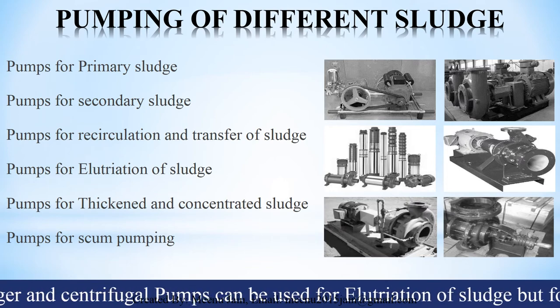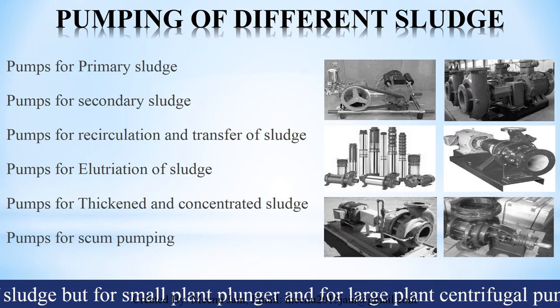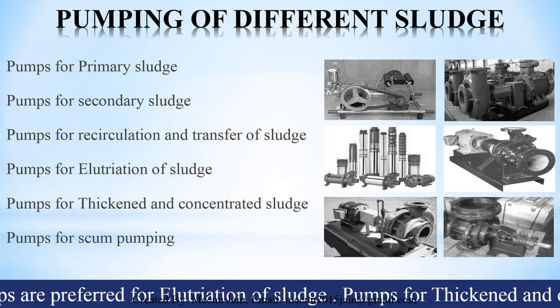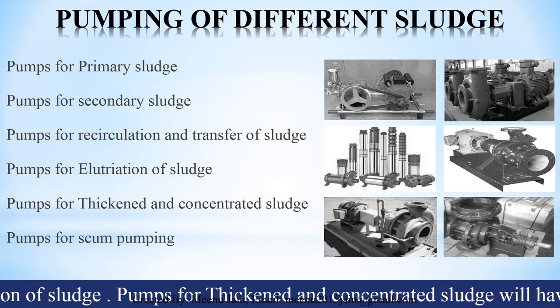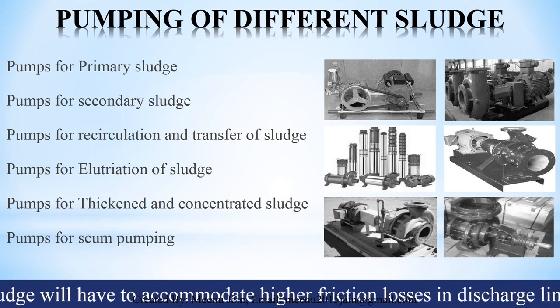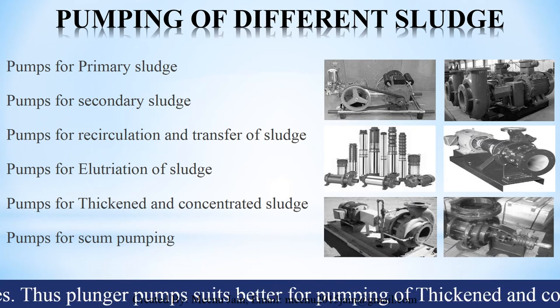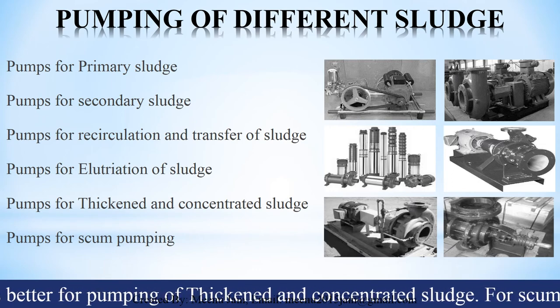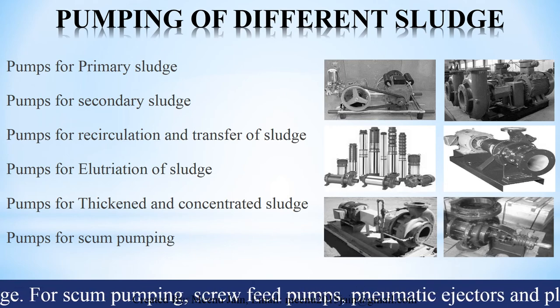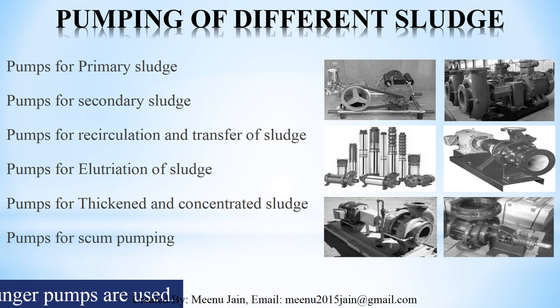Both plunger and centrifugal pumps can be used for elutriation of sludge, but for small plants plunger pumps and for large plants centrifugal pumps are preferred. Pumps for thickened and concentrated sludge will help to accommodate higher friction losses in discharge lines. Thus, plunger pumps suit better for pumping of thickened and concentrated sludge. For scum pumping, screw feed pumps, pneumatic ejectors, and plunger pumps are used.